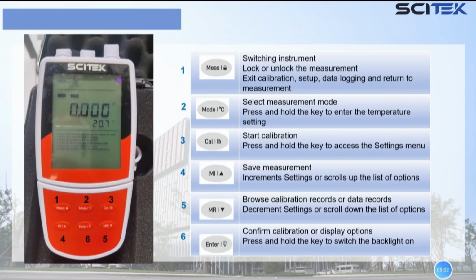Let's see the buttons. This is the measure button, used to turn the instrument on and off and to freeze the measurement value on the screen. If the measurement is frozen, you can press the button again to resume. When you are in calibration mode or setting mode, pressing the button exits and returns to measurement mode. This is the mode button. Press the button to select a measurement mode, such as pH mode, ORP mode, conductivity mode, and TDS mode. Press and hold the button to enter the temperature setting.